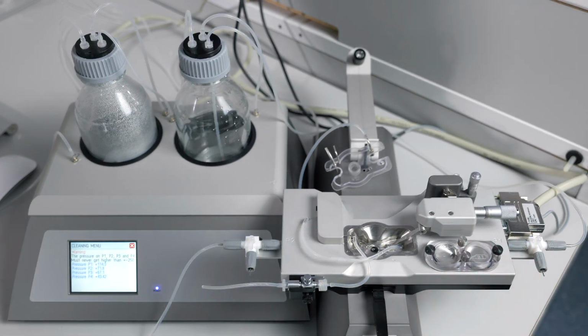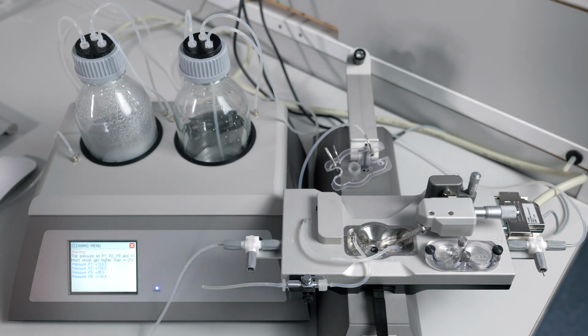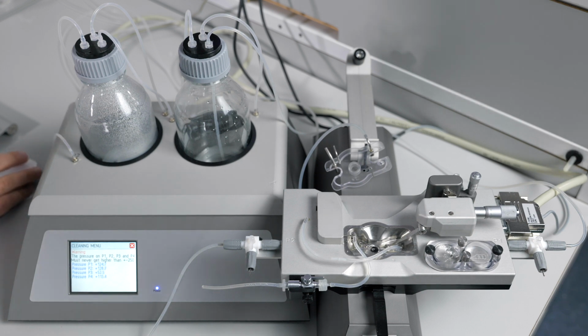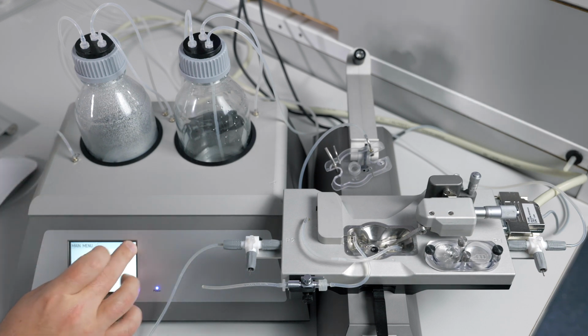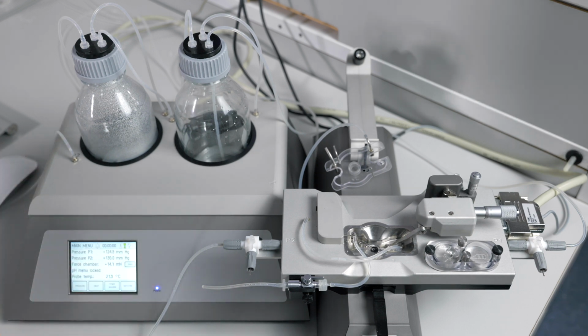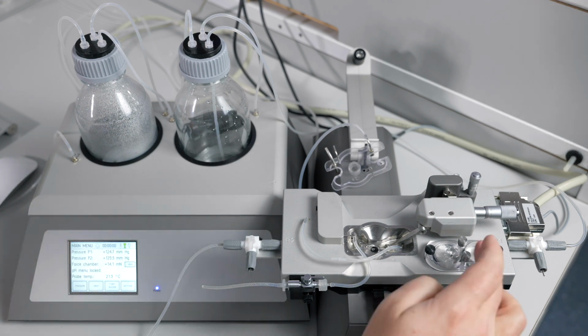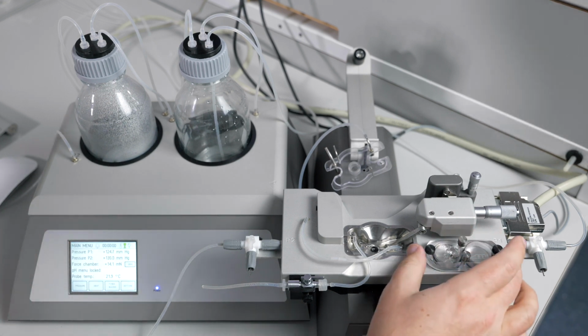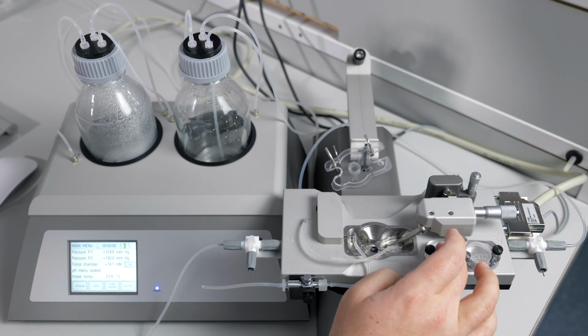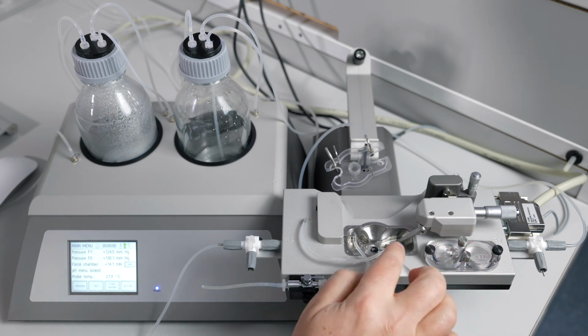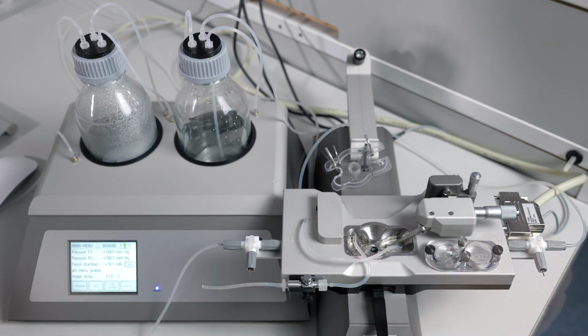Although it is not needed after every experiment, DMT does recommend an 8% acetic acid wash for deeper cleanings. This should only be used if salt debris is clearly visible. After this program has run for 10 minutes, you can stop the pressure and the cleaning menu. The last step is to open the pulsation cover and remove any water from these wells and the tissue chamber itself.